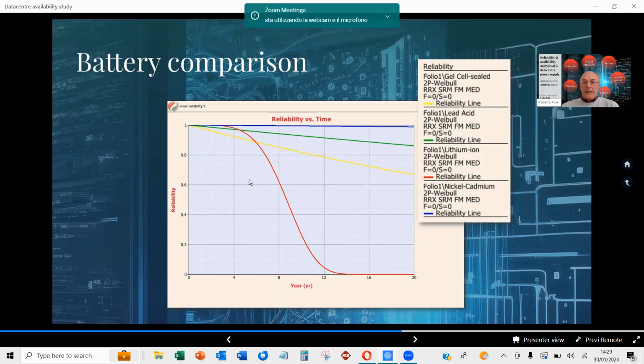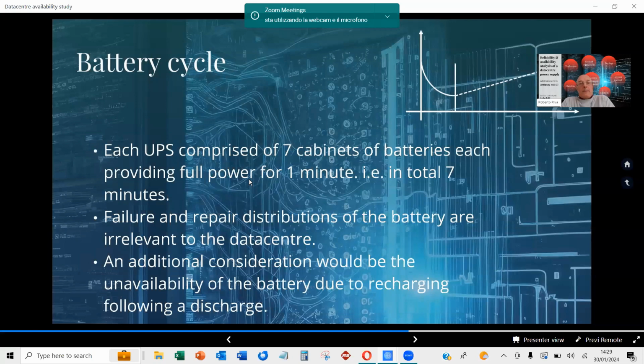We went away with this battery fairly happy, but not fully, because there was another issue we looked into but didn't actually implement. Each UPS in reality is made out of 7 cabinets of batteries, each providing full power for about a minute, giving a total of 7 minutes of coverage during disturbances. If we think about batteries, the failure and repair distribution is in a sense irrelevant to the data center - it's more the recharging that worries us.